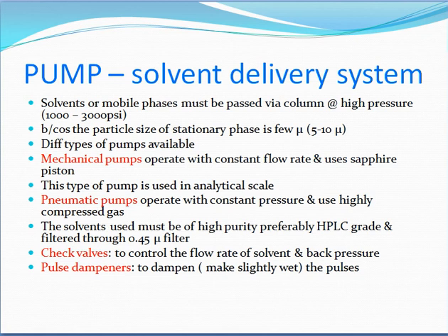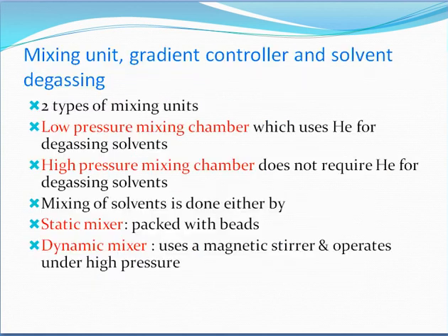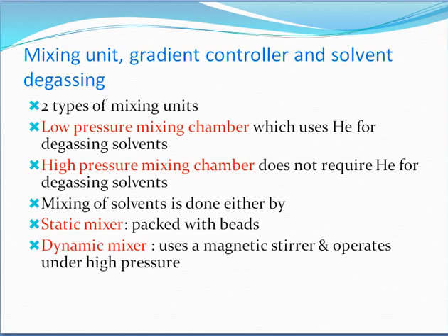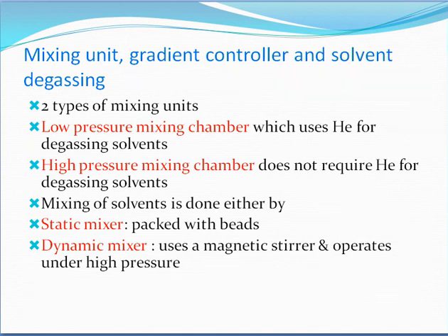The mixing unit includes a gradient controller and solvent degassing system. There are two types of mixing units: a low pressure mixing chamber, used for degassing solvents, and a high pressure mixing chamber. Mixing of solvents is done either by a static mixer, which is packed with beads, or a dynamic mixer.